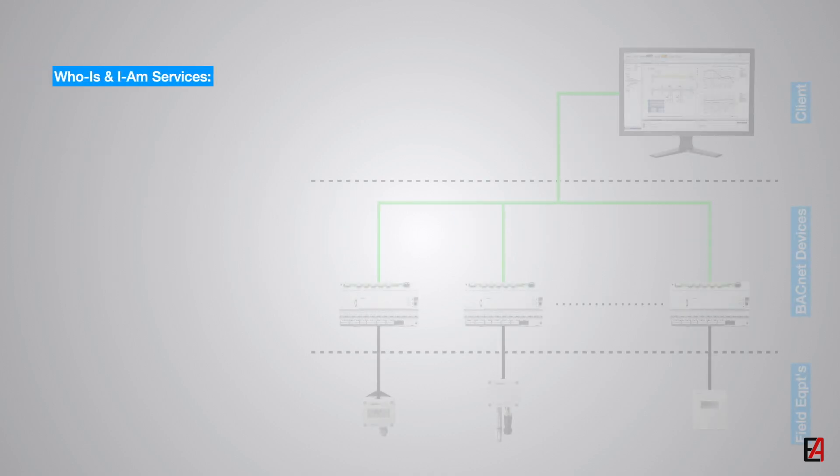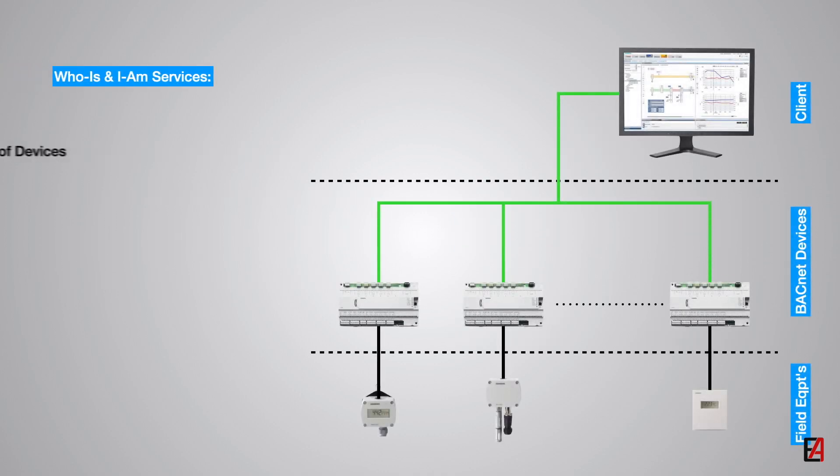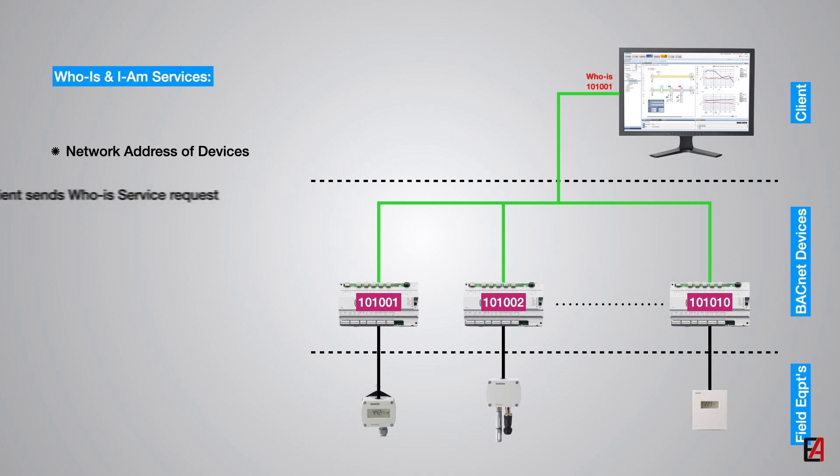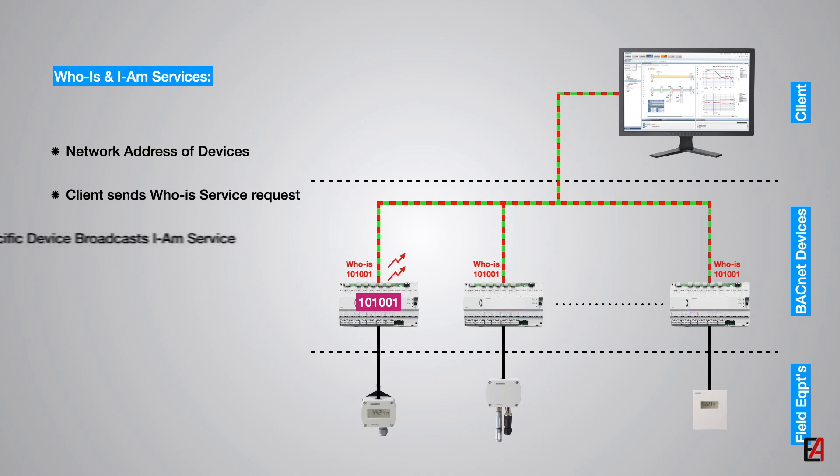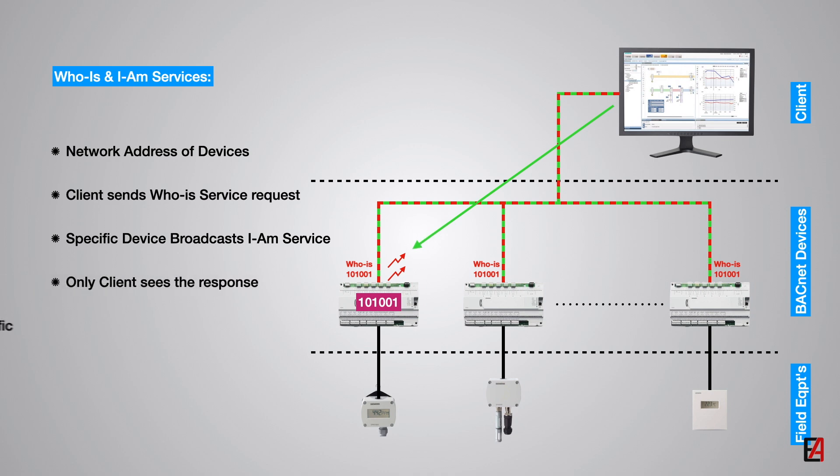Next is the WHOIS and IAM services. This is used to obtain network addresses of BACnet devices on a BACnet network. A BACnet device that needs to know the address of a device can broadcast WHOIS service request on the BACnet network. Specifying a device object instance number, the responses do not come back as a reply. Instead, the device that has specific device object broadcasts an IAM service. This allows the client to acquire the information from the specific device without creating more network traffic.